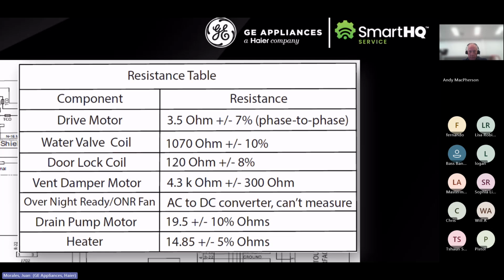So that would be between your three connectors, you should have about 3.5 ohms. If we look at the water valve right below, 1070 ohms on the coils. So if you place your meter leads across the solenoid, you should get about 1070 ohms. And of course, your drain pump is about 19.5 ohms, plus or minus 10%.